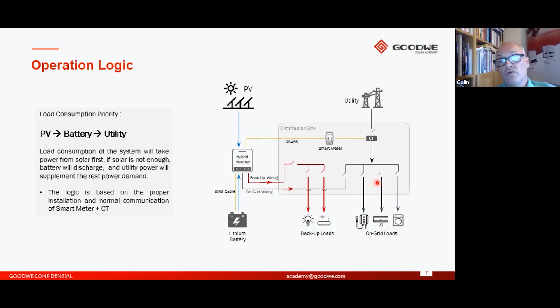What we need to look at here is what happens when we lose the grid connection. As you can see here on the right-hand side, all the AC connected devices are now disconnected because we've lost the grid. That only leaves the power available from the inverter via the PV that's generated and the battery. This is only sent to the devices which are connected on the AC backup port.